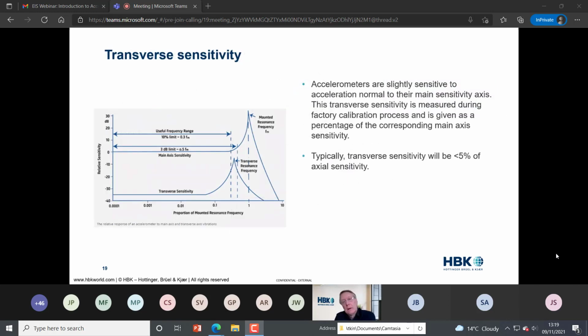Now, unfortunately, piezoelectric accelerometers do have some transverse sensitivity as well. Ideally, if you mount an accelerometer onto a surface, you want it only to be measuring in the primary axis of the accelerometer, but there is a transverse sensitivity as well, as you can see on this graph here. Fortunately, the transverse sensitivity is generally less than 5% of the axial sensitivity, but it's something to bear in mind depending upon the application.